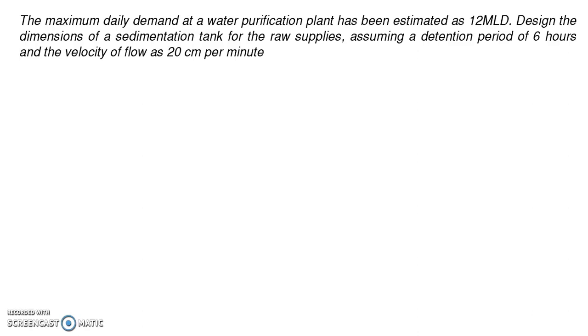According to the problem statement, what we have here: the daily demand is 12 million liters, i.e., 12 × 10⁶ liters daily — that means for a 24-hour time span. The retention period given is 6 hours, meaning for every 6 hours you supply another batch of water. The velocity of flow is 20 centimeters per minute, which can be converted to 0.2 meters per minute.